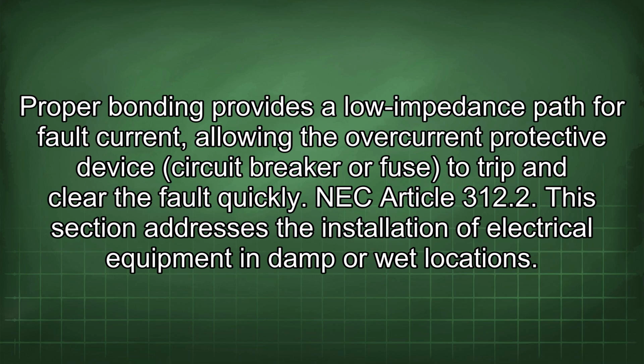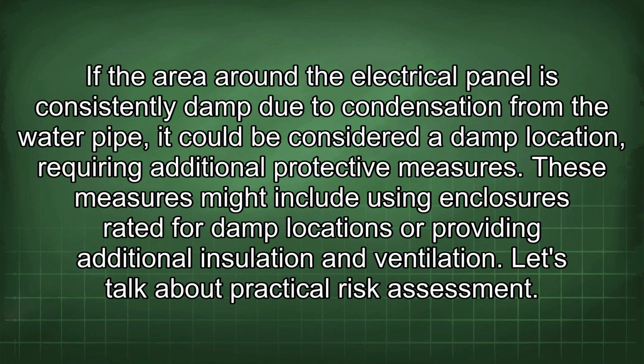NEC Article 312.2. This section addresses the installation of electrical equipment in damp or wet locations. If the area around the electrical panel is consistently damp due to condensation from the water pipe, it could be considered a damp location requiring additional protective measures. These measures might include using enclosures rated for damp locations or providing additional insulation and ventilation.